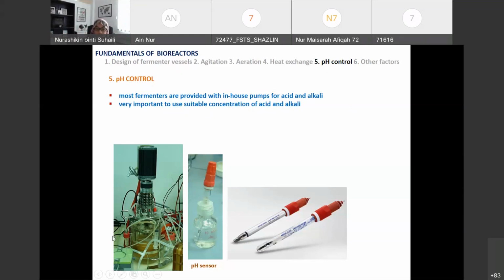So the alkali, the base, will be added based on the instruction given by the control unit. Once it detects the pH below 7, it will add some alkali until it reaches 7. When it reaches 7, it stops the addition of base, and vice versa. If the pH is basic, more than 7, and you want to bring it back to 7, then you have to add a little acid, but it will be automated. That's the importance of automation for bioreactors, because it will be controlled by the bioreactor. You don't have to add the acid by yourself. Modern bioreactors have all these kinds of things.